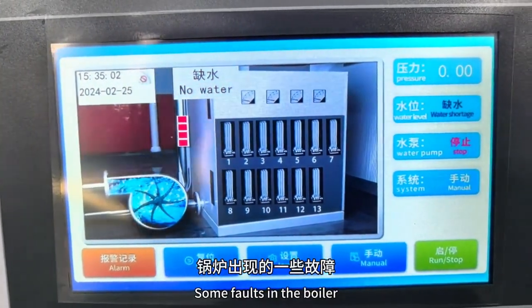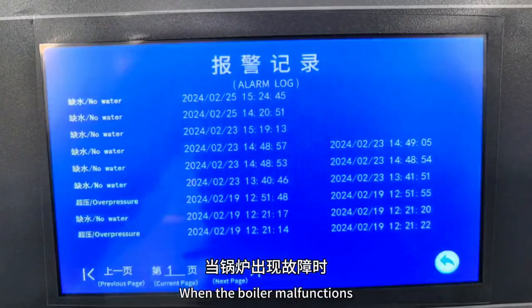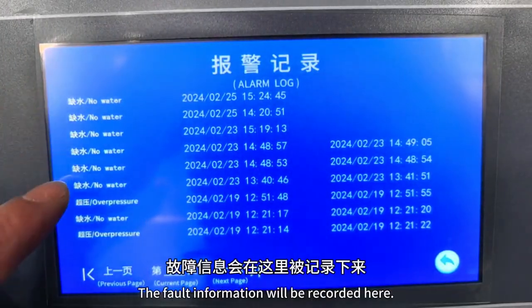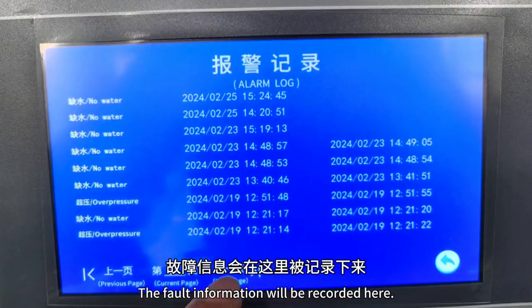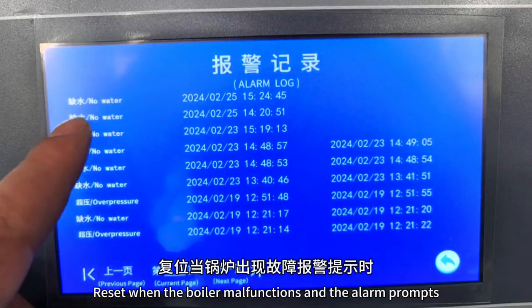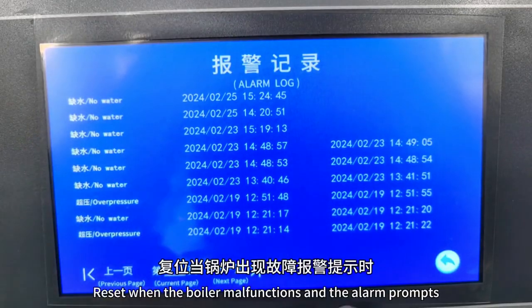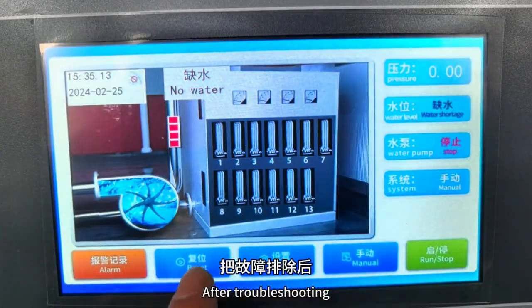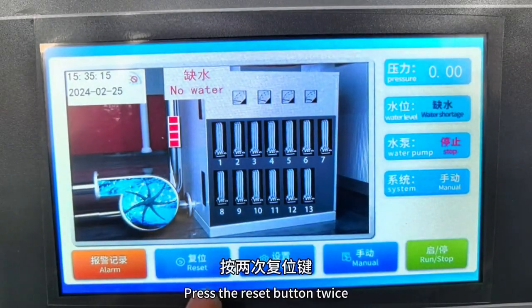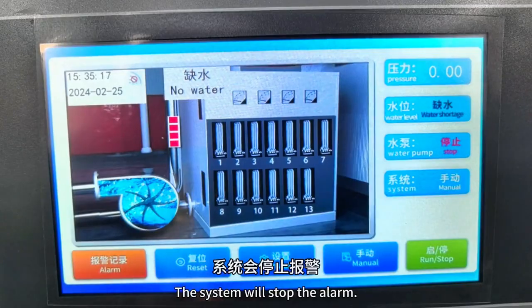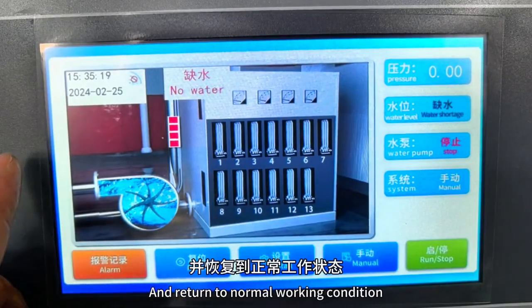Alarm record is used to view some faults that occur in the boiler during a certain period of time. When the boiler malfunctions, the fault information will be recorded here. When there is a fault alarm prompt in the boiler, after troubleshooting, press the reset button twice, and the system will stop the alarm and return to normal working state.